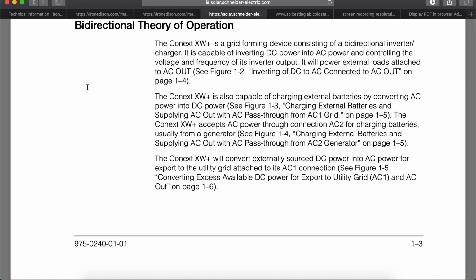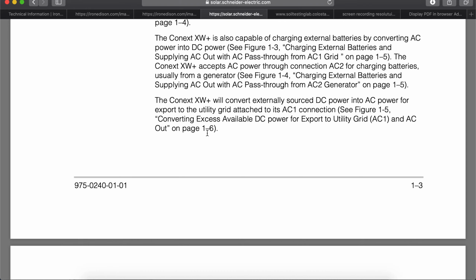And you have the ability to go in and manually turn on and off that charging capability. For example, if you don't want to charge from the grid, if you just want to use the grid to keep the system operational when the battery is low, that's a good way to minimize AC input but maximize system reliability. The Conext XW Plus inverter charger will convert externally sourced DC power, solar, battery, even wind and hydro, into AC power for export to the utility grid, back out of its AC1 connection. See Figure 1-5, converting excess available DC power for export to the utility grid, AC1 and AC out, on page 1-6.